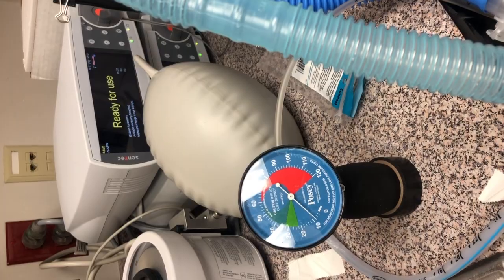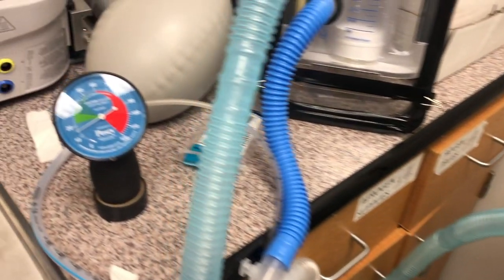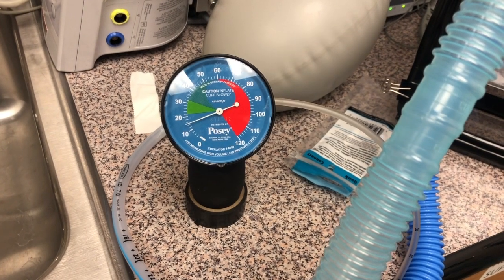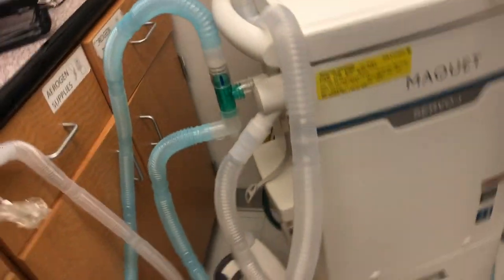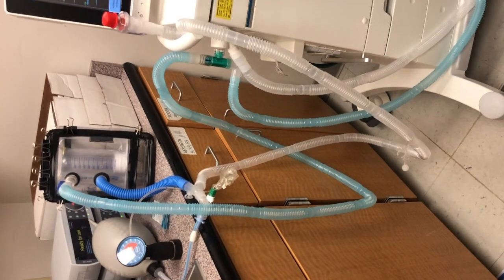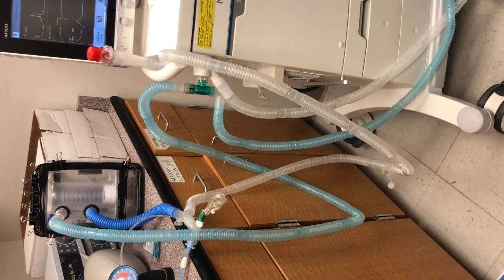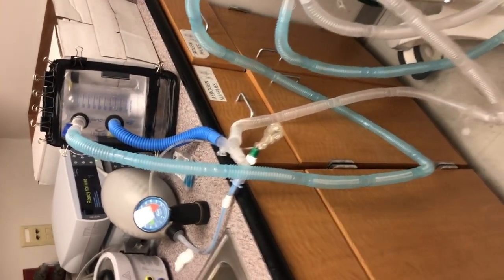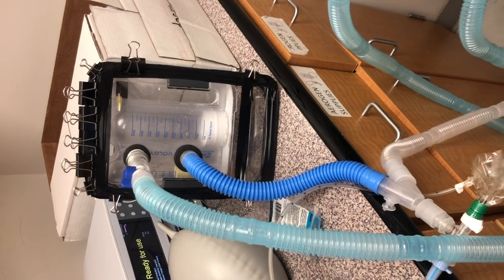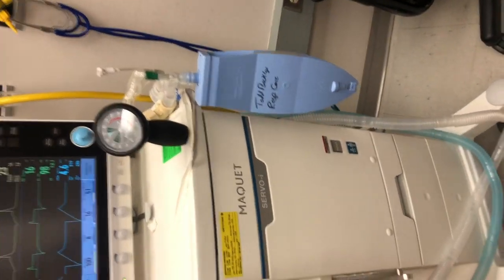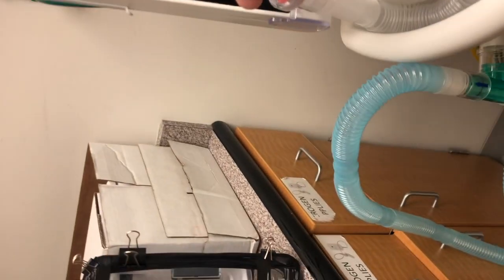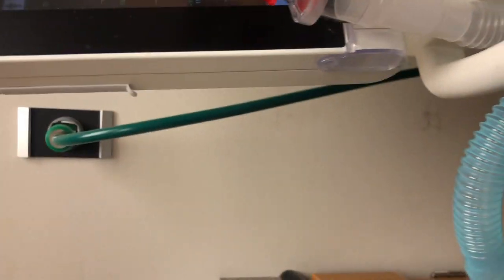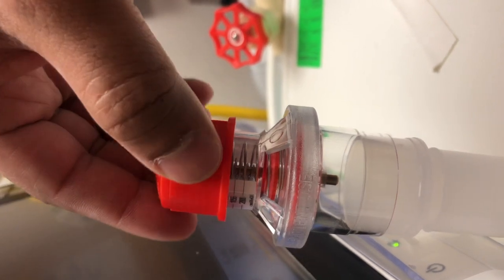Now here, if you see, I have adjusted the PEEP to be 8, which is the inherent PEEP of the ventilator, and I have changed PEEP on the first lung to 12, and this is the circuit with the peak flow meter attached. Again, I have not made this a closed circuit because of time constraints, and as different PEEP may not be needed all the time. Now I am changing the PEEP with a peak flow meter. If you see, and lowering it again, and if you see, the PEEP is lowered to 8.